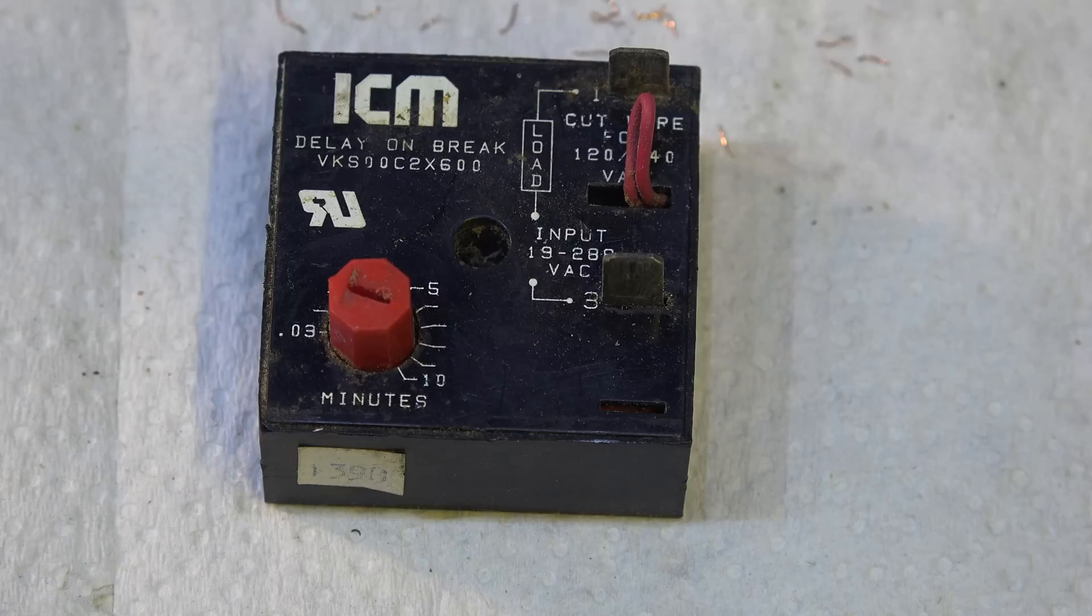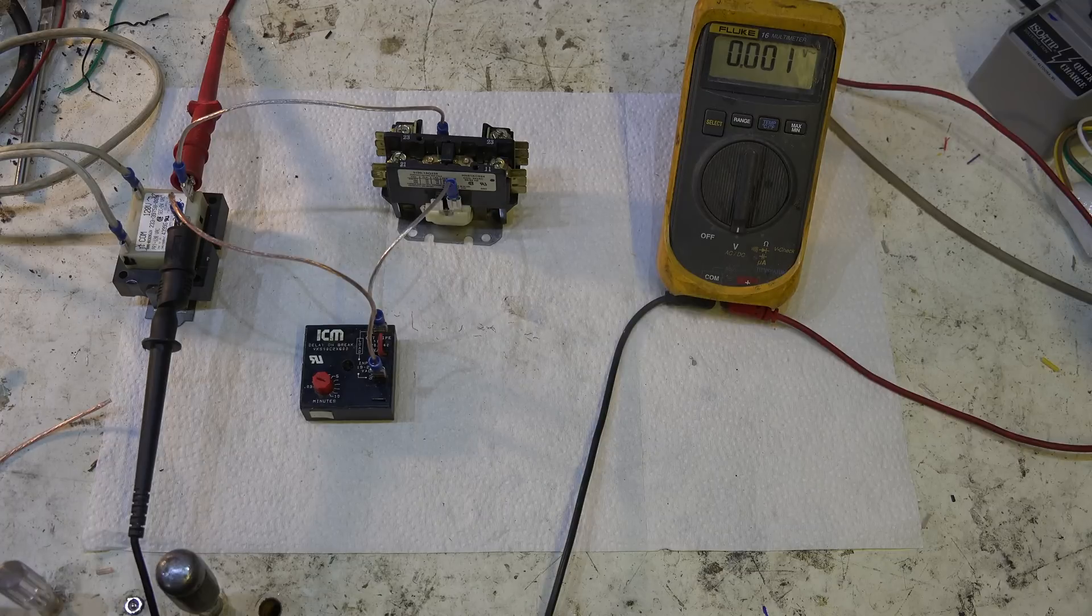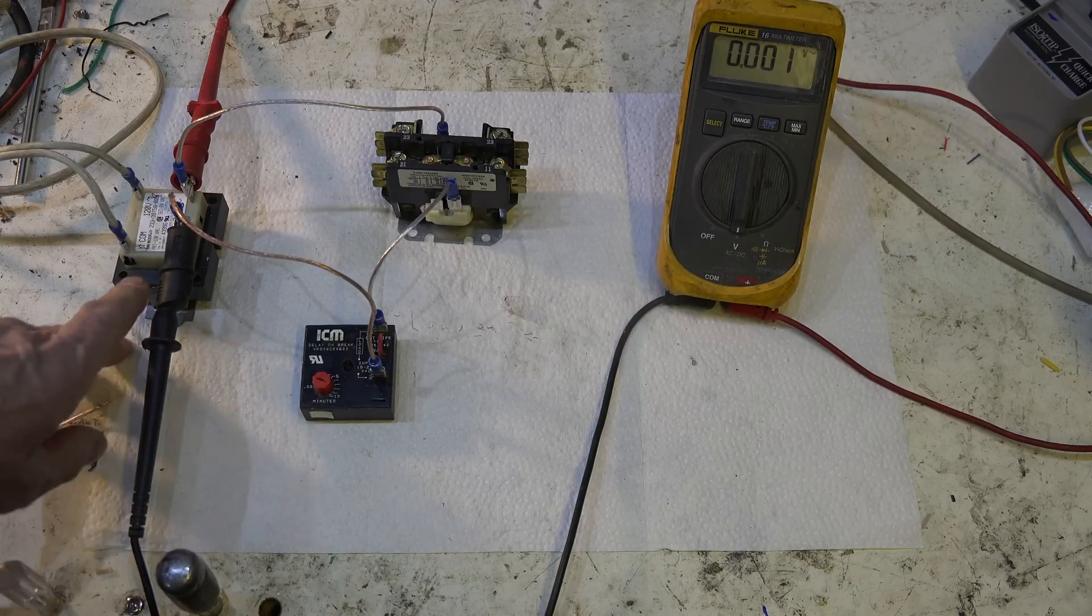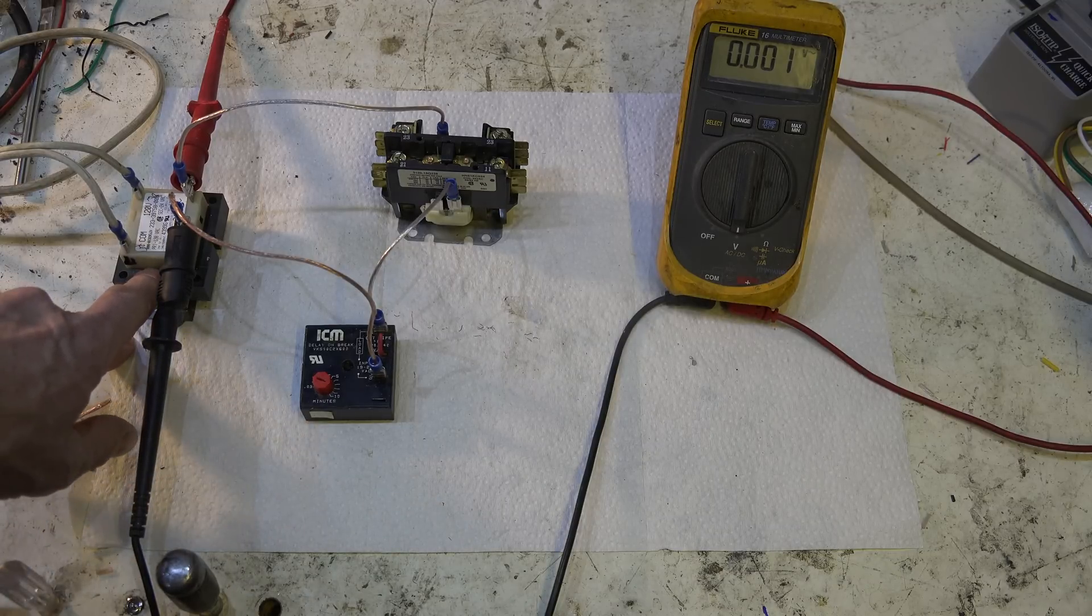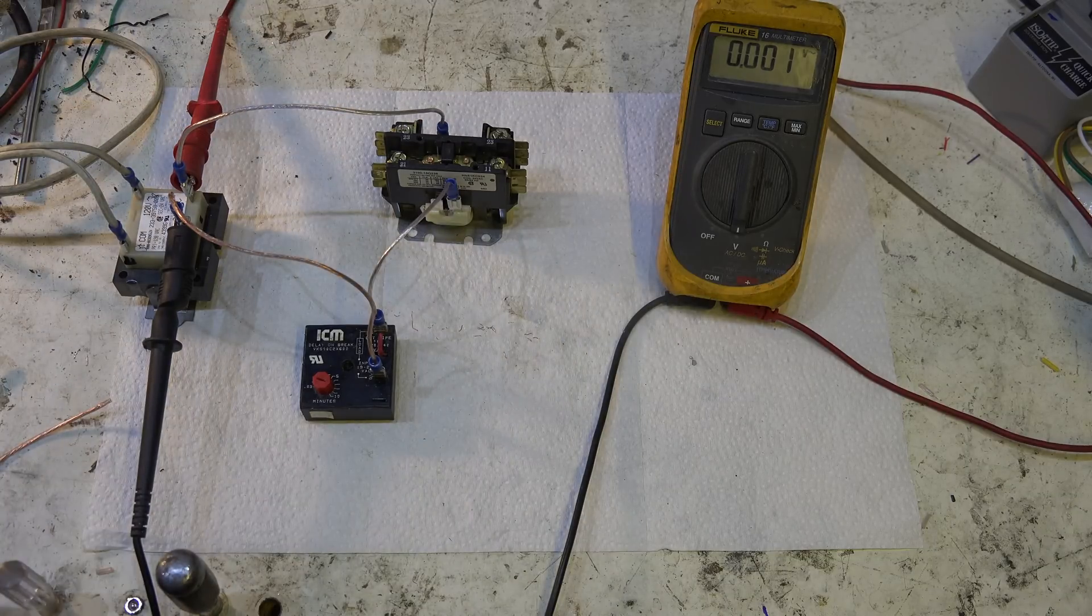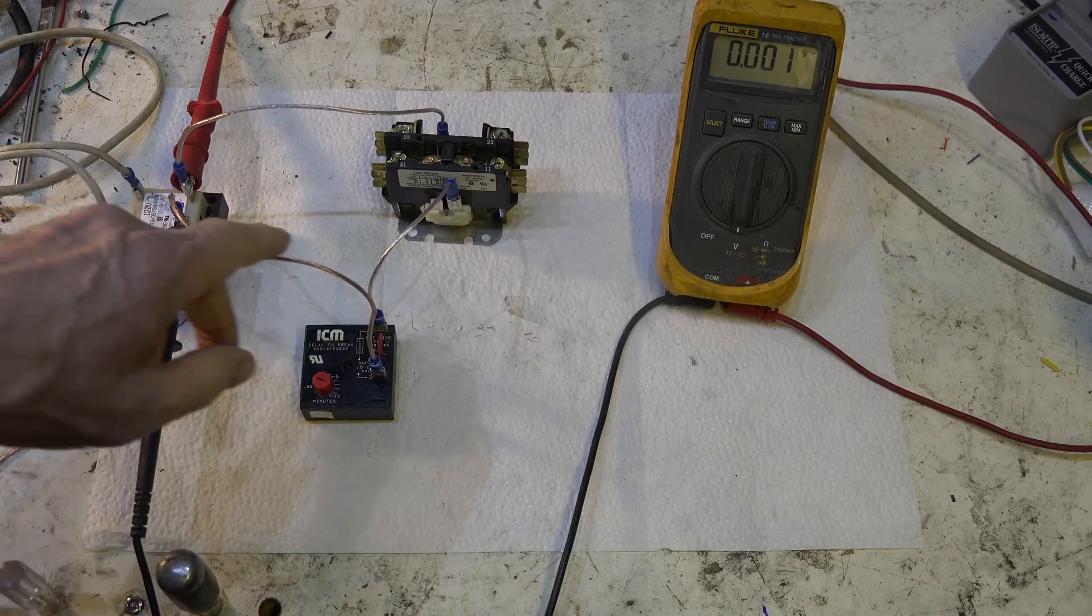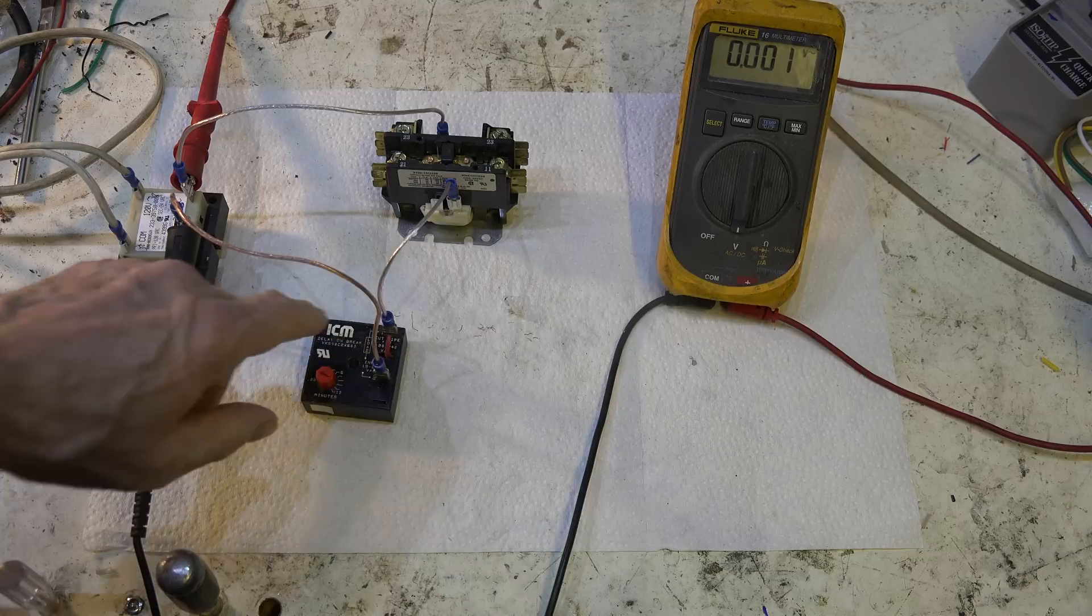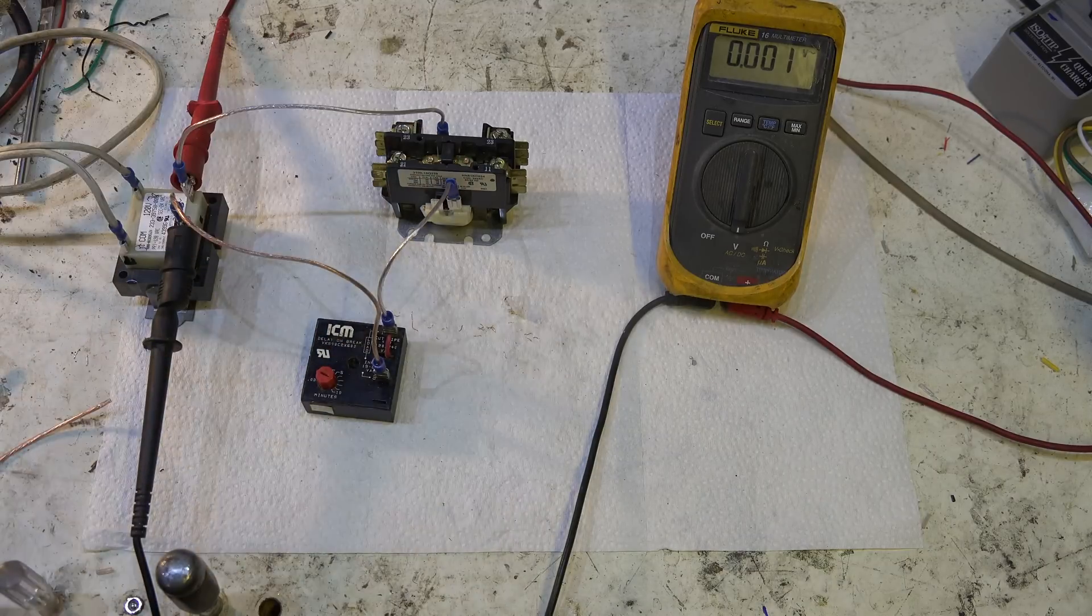Now I'm gonna show you the setup we have here. I've just taken a 24 volt transformer. I've hooked one common side to a contactor. I've taken the other side and run it through this control to the contactor, so this is feeding the coil of the contactor 24 volts.